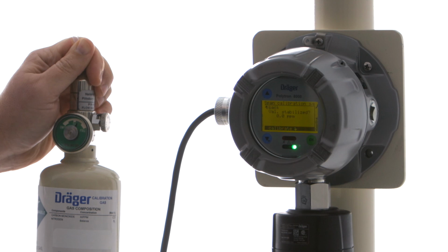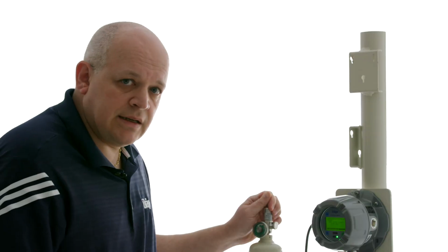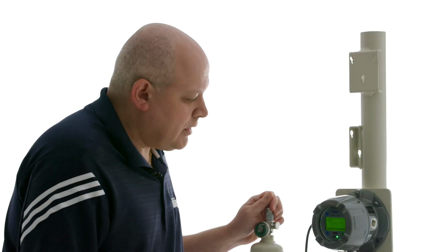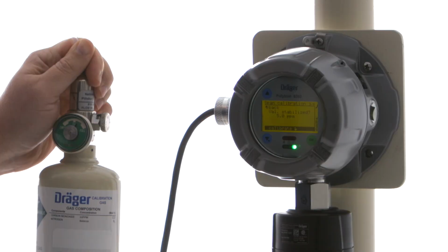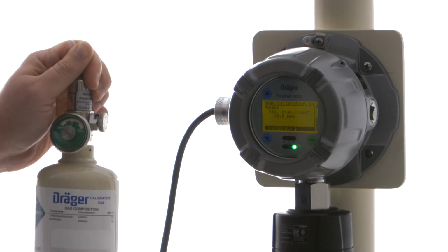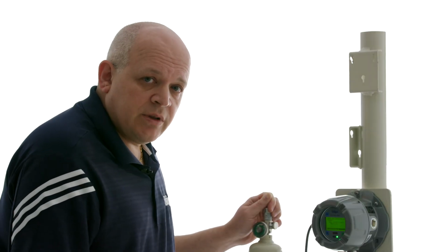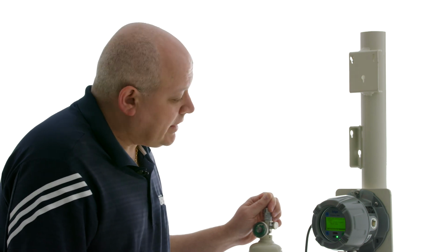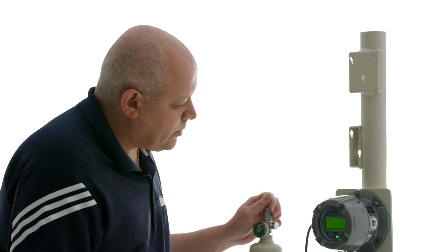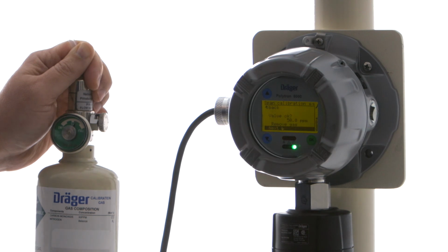And here again, we're going to watch for the value to be stabilized. It doesn't necessarily have to reach 50 ppm. It just has to be stable. Okay, it's been a couple of minutes. Our value is stabilized at 50 ppm. If for some reason it's stabilized at 52 or say 53, that still would be okay. We simply just have to hit select OK to calibrate.